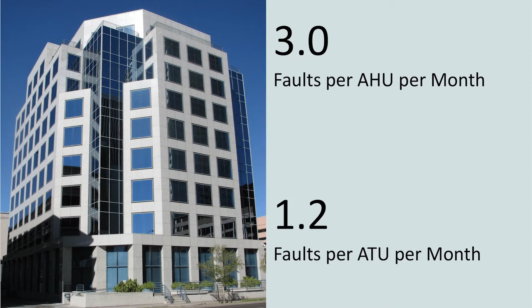If you want to normalize that to individual units, for an air handler we found there's typically about 3 faults per air handler per month, and just over 1 fault per month for terminal units—which is really going to add up if you've got hundreds of terminal units in your building. So that's the first piece here, just talking about the volume of faults.